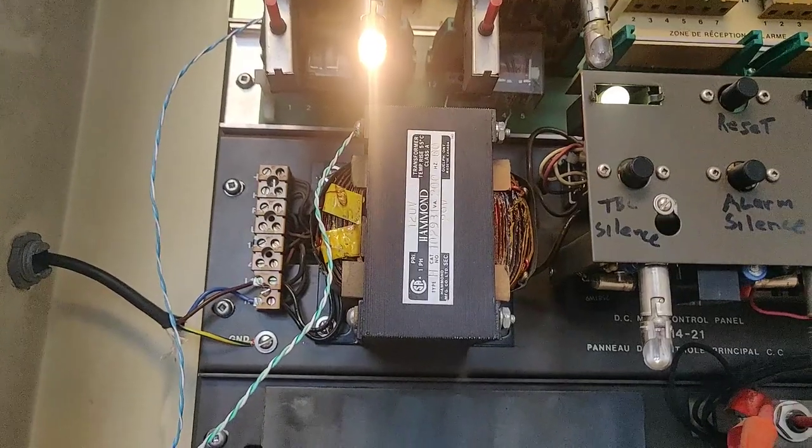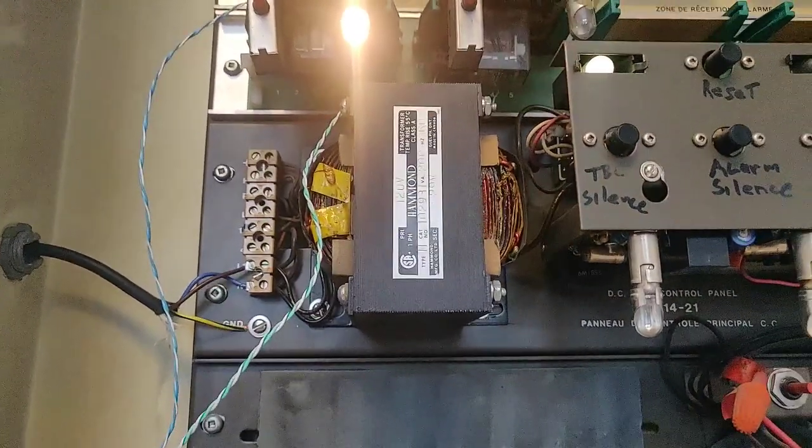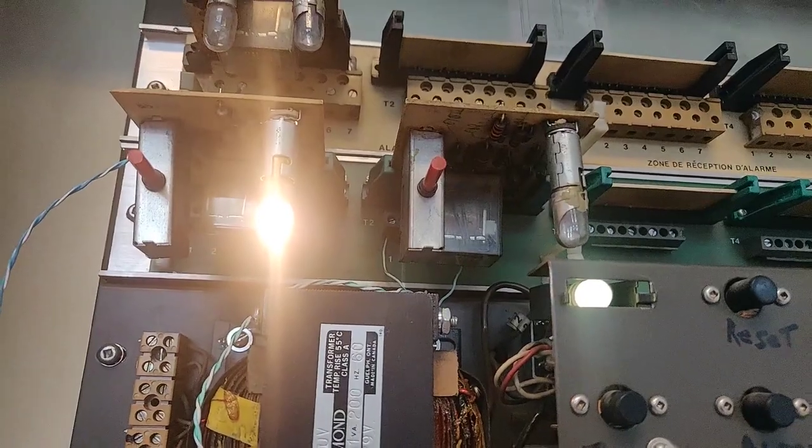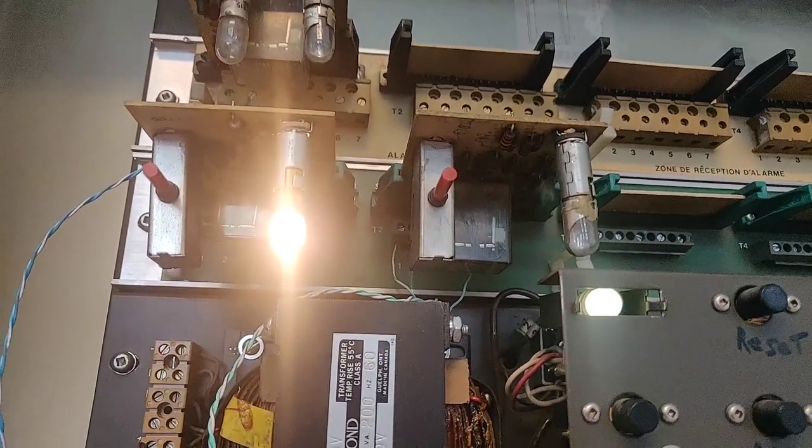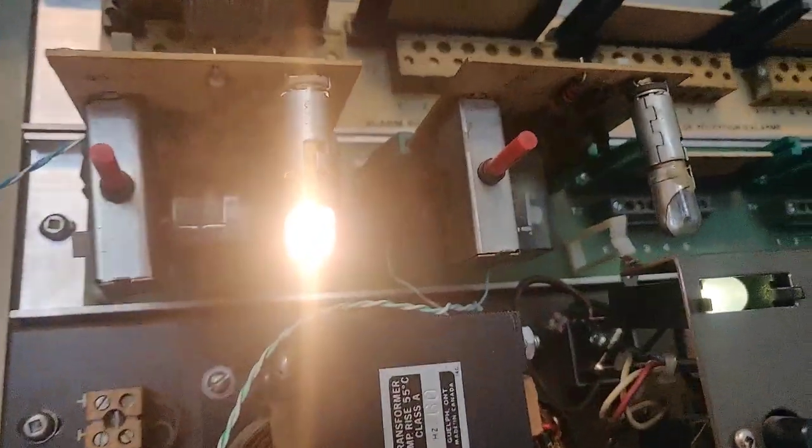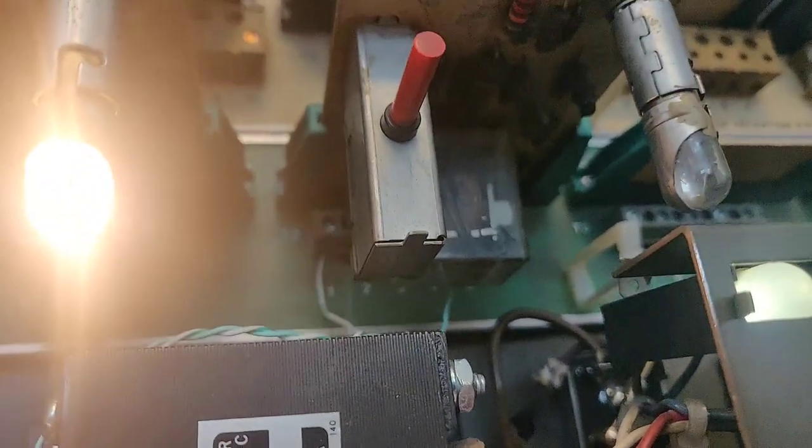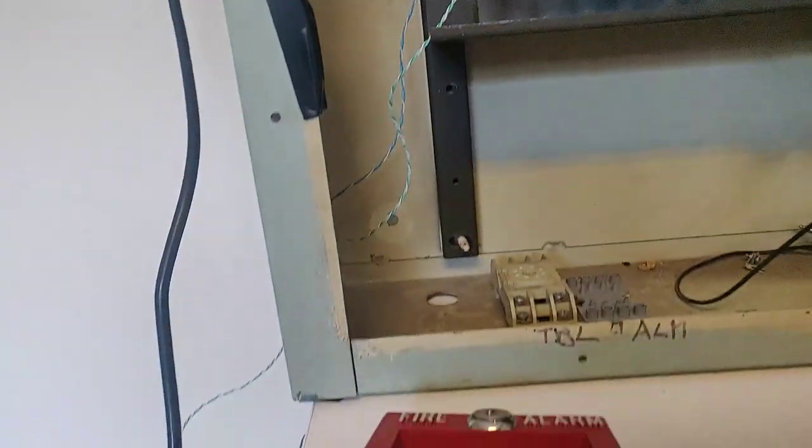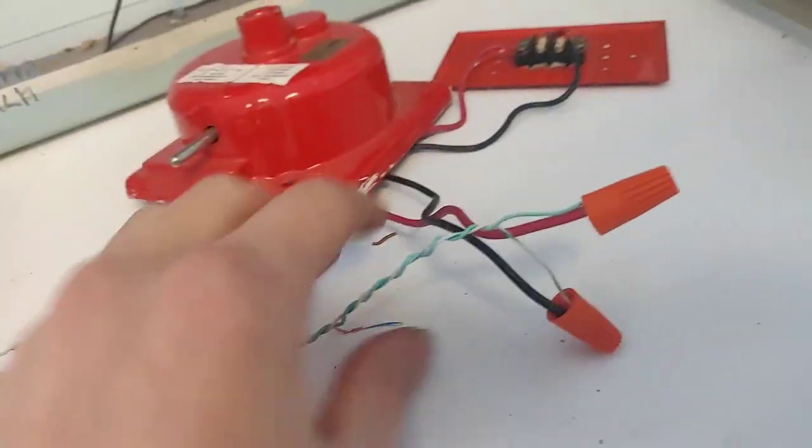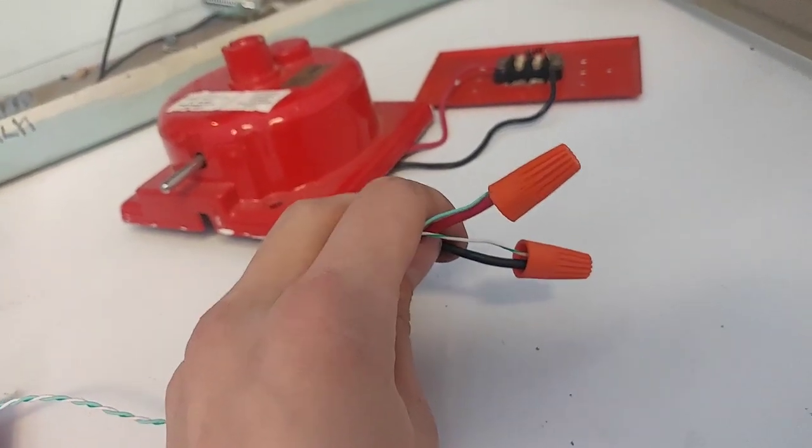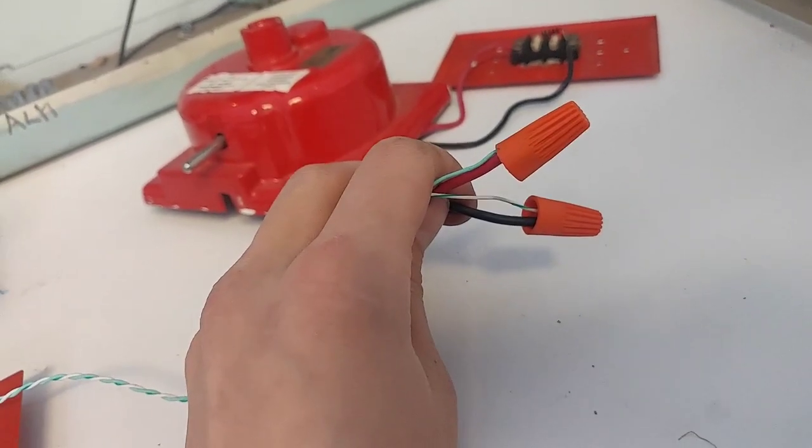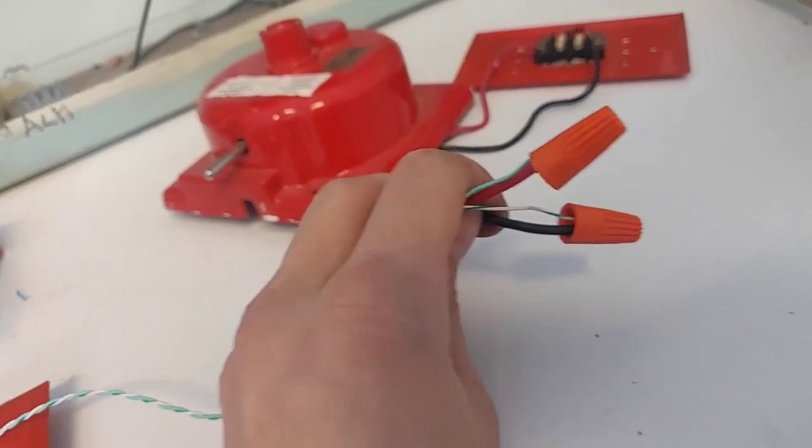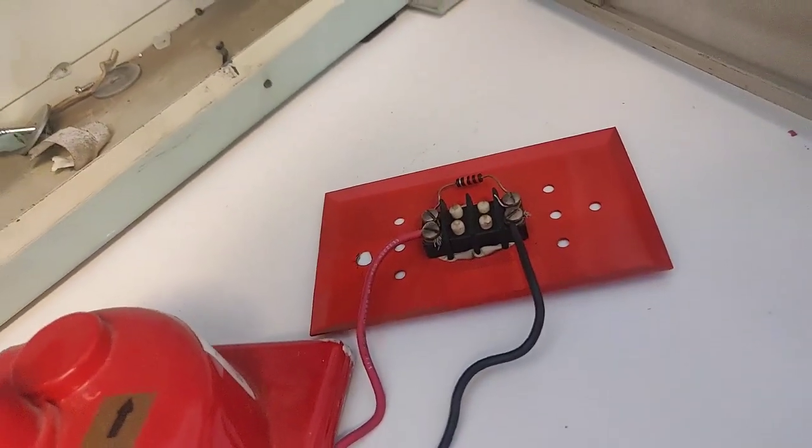So there you go. So now let's move on to our bell circuit. So now I've got the bell circuit wired in a class B manner. It wires exactly the same as the pull stations or initiating circuit does—just instead of pull stations you have notification devices. So you can see terminals 1 and 4 and 2 and 3 are for the return. So 1 and 4 come back and it goes off to the bell. It's imperative that every bell in the circuit is wired with correct polarity, or it won't work. It'll give it trouble. And then at the end we have again the same resistor.